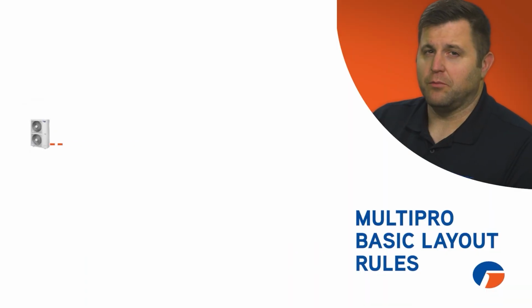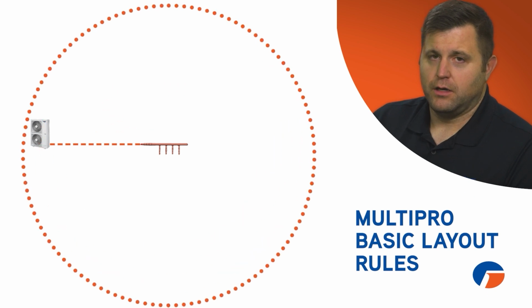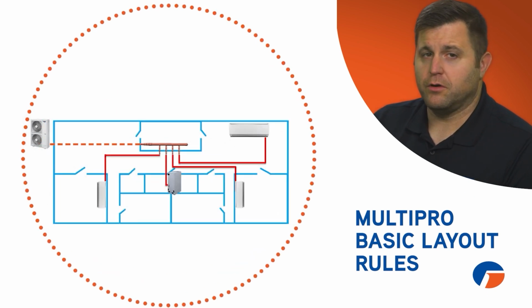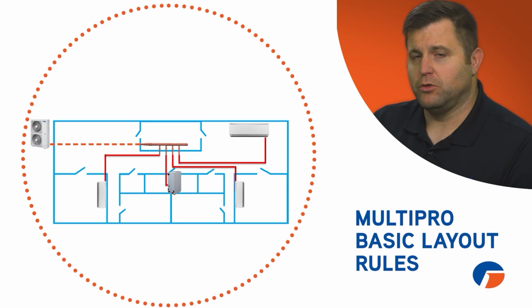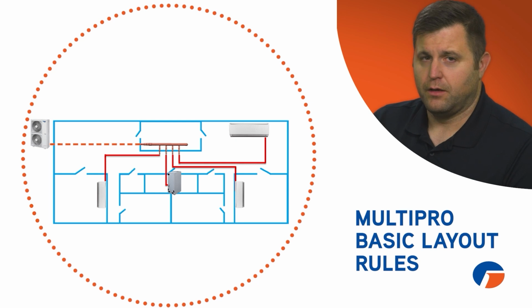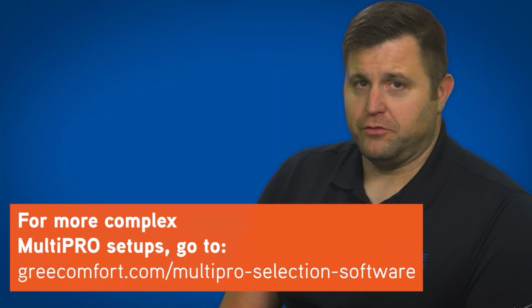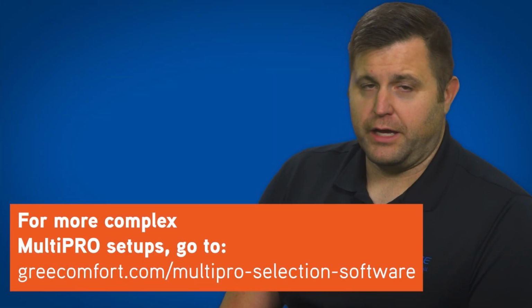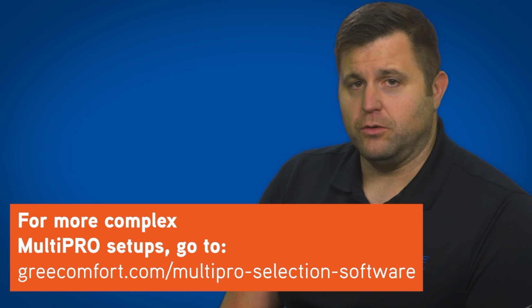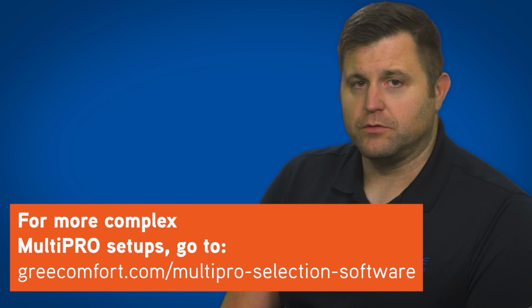30 feet may seem a bit short, but think about it like this. A Y branch or header will have a radius of 30 feet all the way around it. If that were placed in the center of a building, you could hypothetically cover a space of more than 2,800 square feet. How many spaces of that size require less than 5 tons? Almost none. But if you do come across a job that won't meet the specs of a basic layout, our MultiPRO Selector is easy to use and provides a printout that includes system information like piping and wiring diagrams.